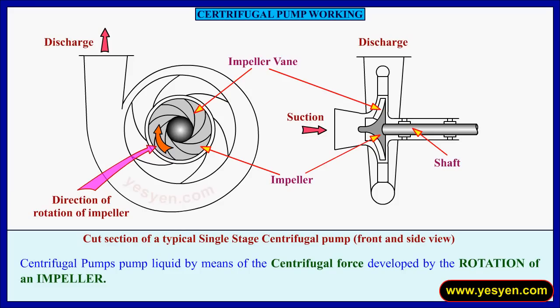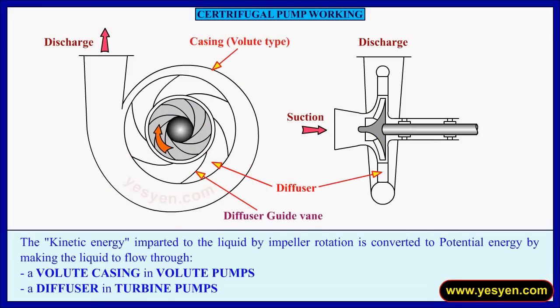Centrifugal pumps pump liquid by means of the centrifugal force developed by rotation of an impeller. The kinetic energy imparted to the liquid by impeller rotation is converted to potential energy by making the liquid flow through a volute casing in volute pumps, or a diffuser in turbine pumps.